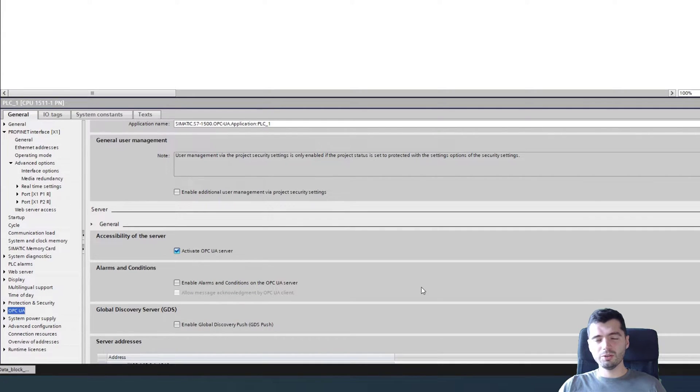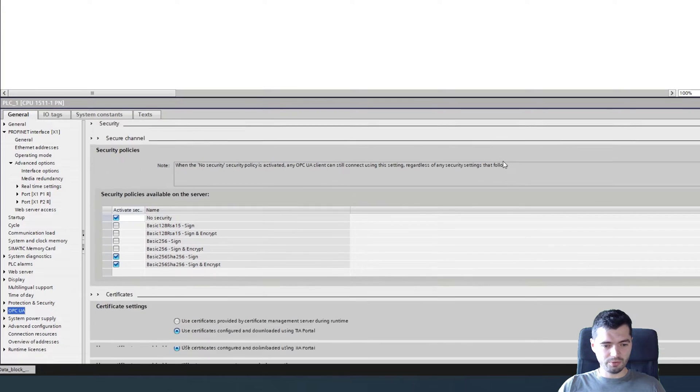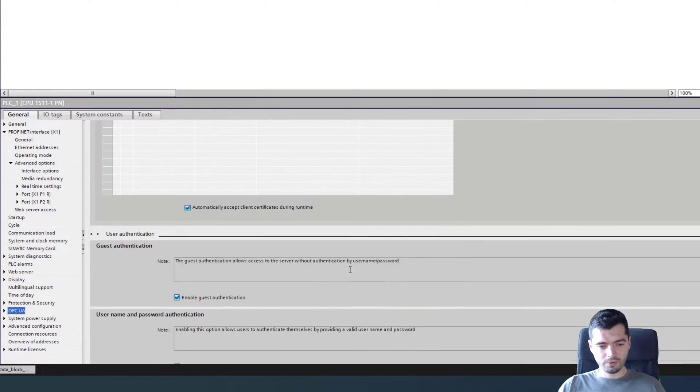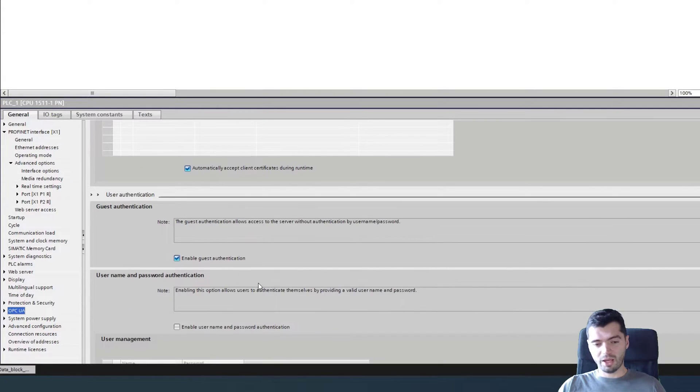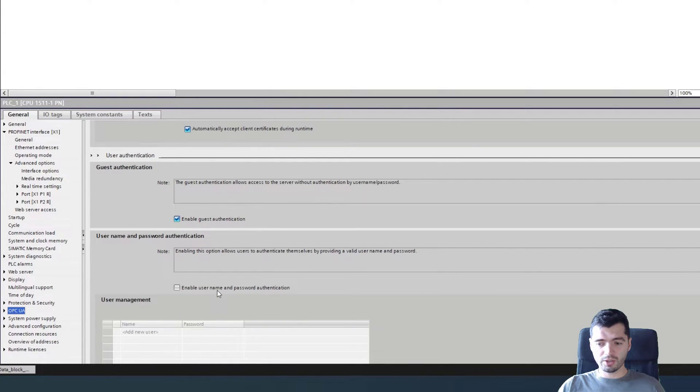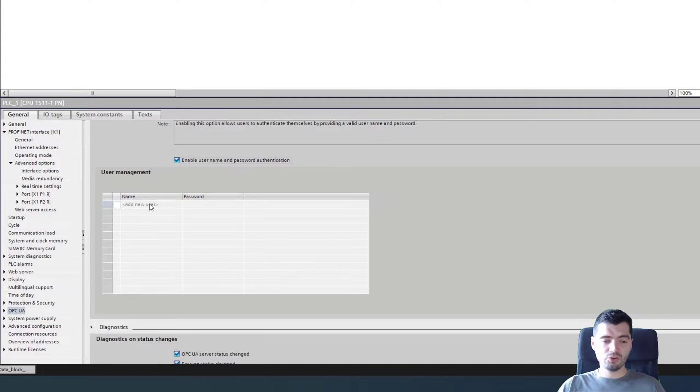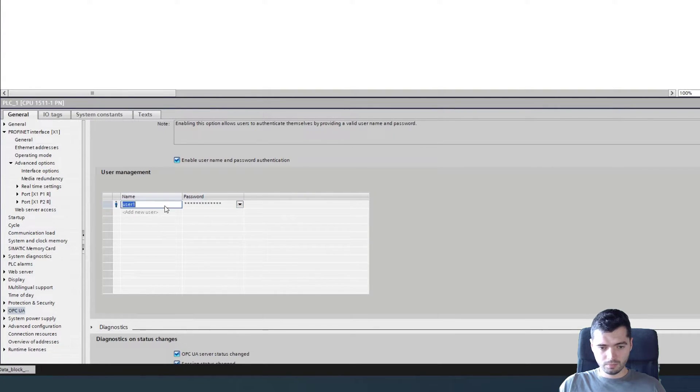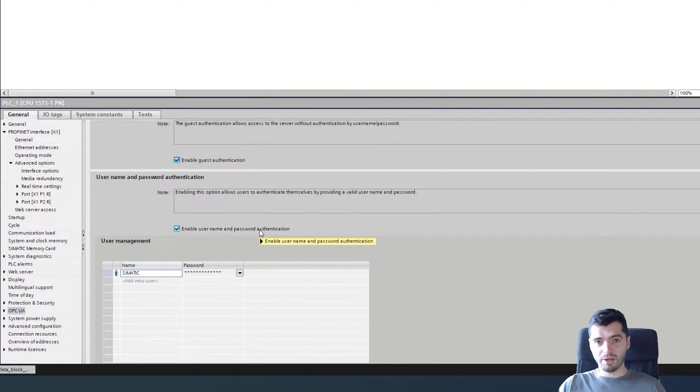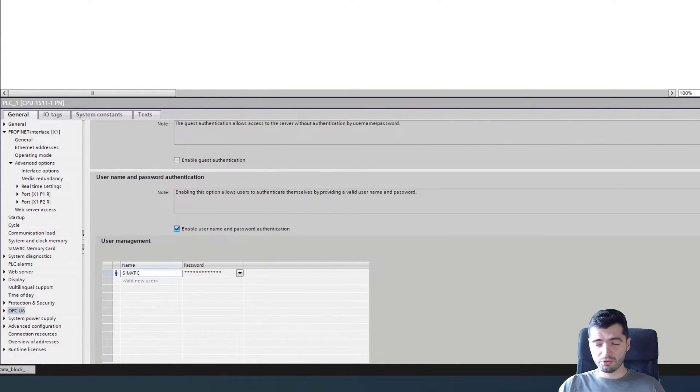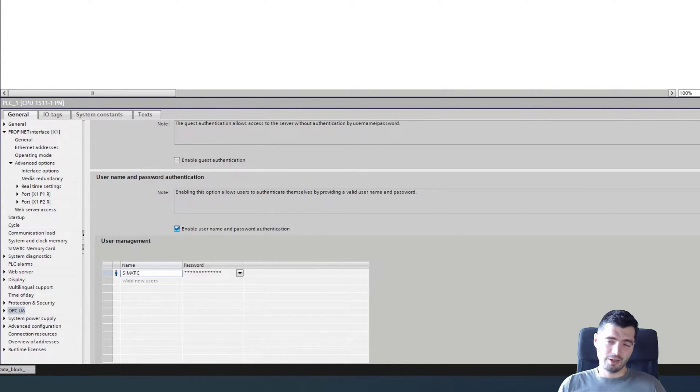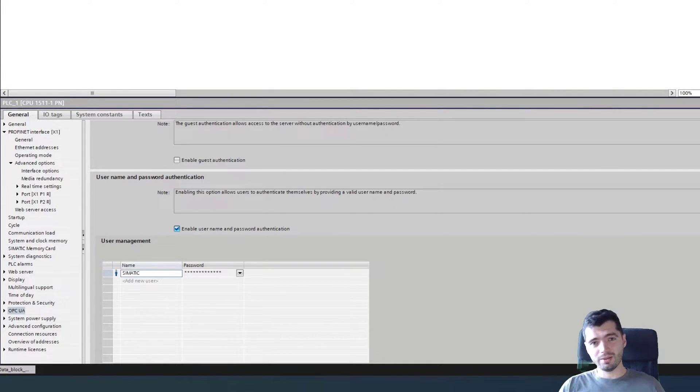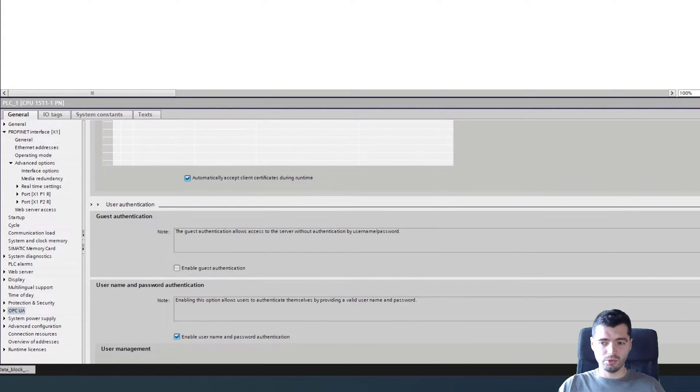Then depending on your requirements, you can either leave it unprotected. If you scroll down here, you can enable guest authentication, which basically means that anyone will have access to this. Or you can start doing things like username and password authentication, where I can manually add a new user. So if I leave it like this, I will have username and password authentication, but I still have guest authentication. So anyone would have access to this data. I would advise against this, maybe disable the guest authentication. Although if you have any problems with OPC UA, then for troubleshooting, I would say enable guest authentication and make sure you can connect with guest authentication. Because if you can't connect this way, then most likely any other way won't work.